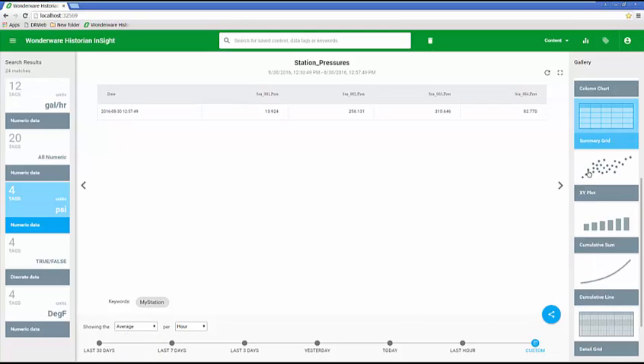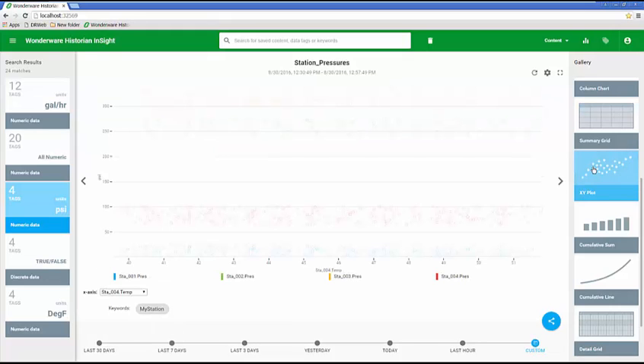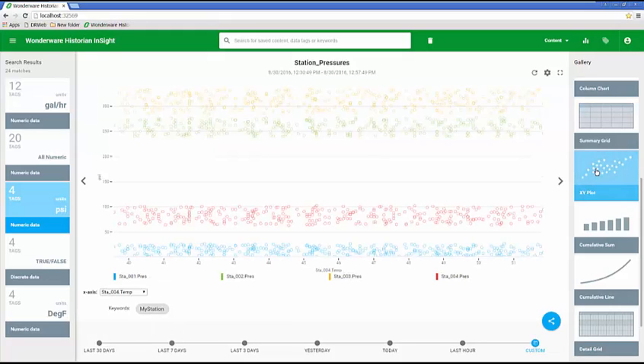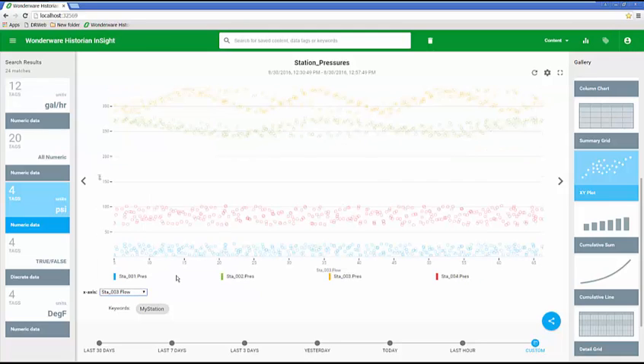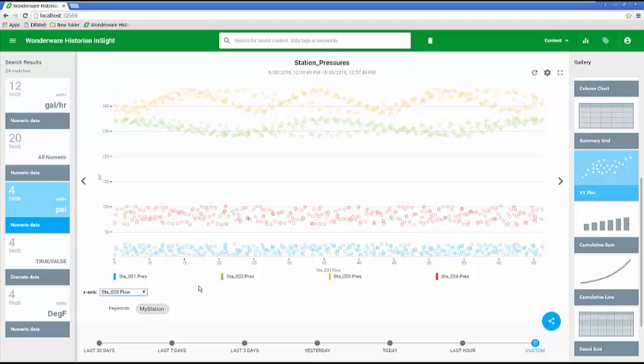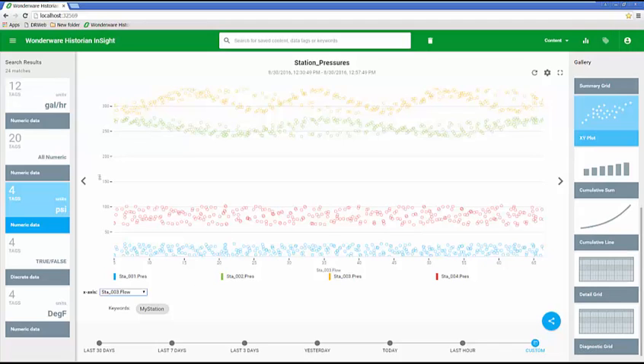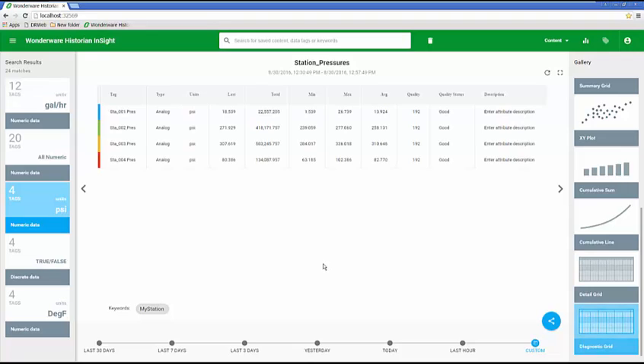There is an XY scatter plot if I want to look at data that way. I can choose my x-axis, like taking these pressures against my flow, and it's going to plot that in XY type format. There is another grid called a diagnostic grid showing me all the values, my last value, total, min, max, average, and my quality, whether I'm getting good information from my PLC.